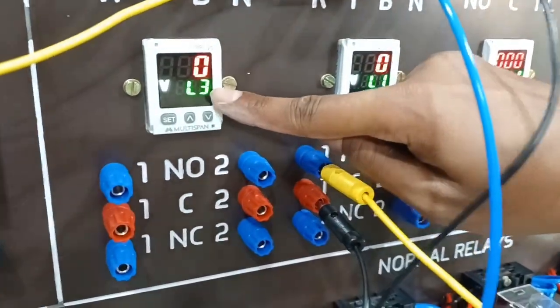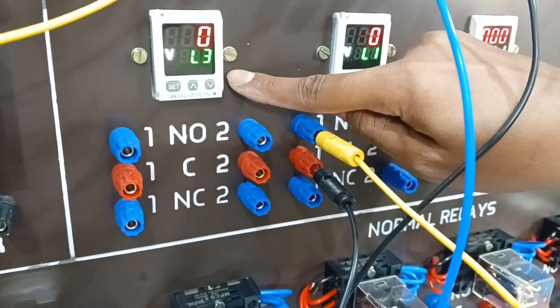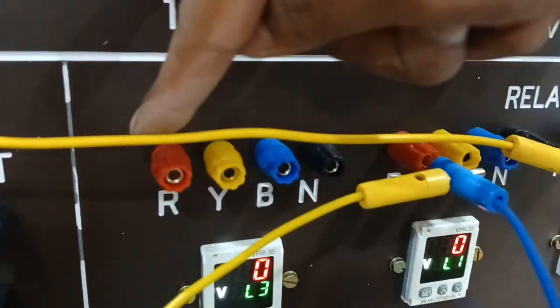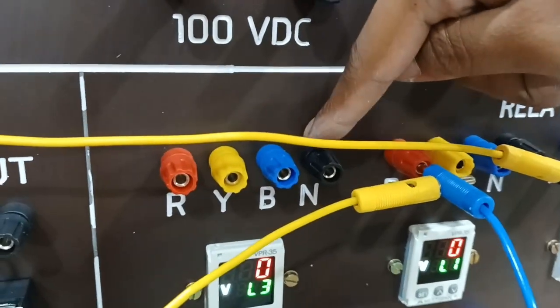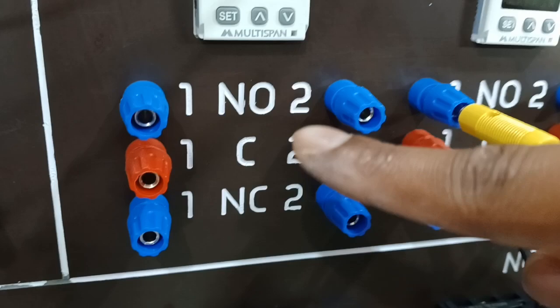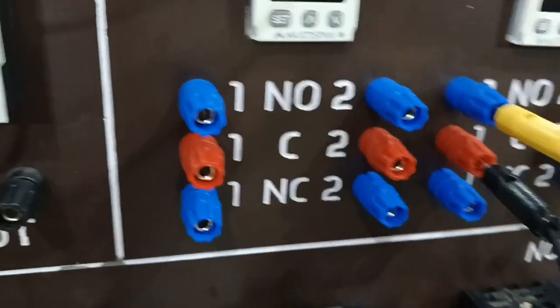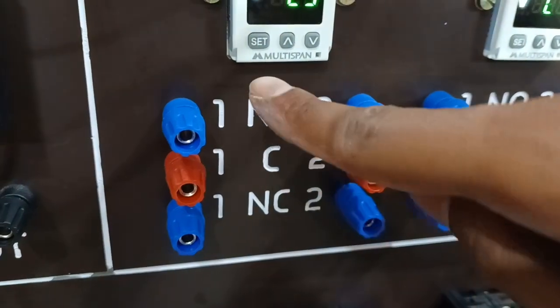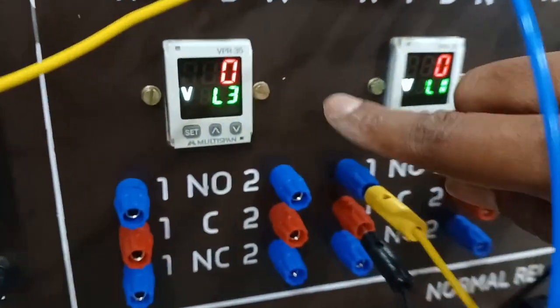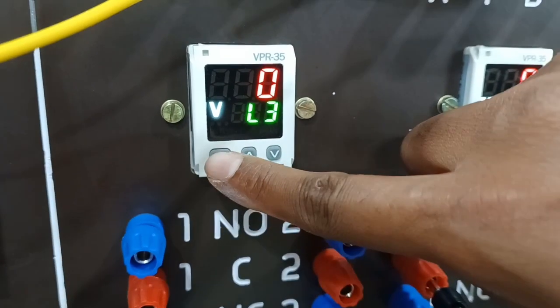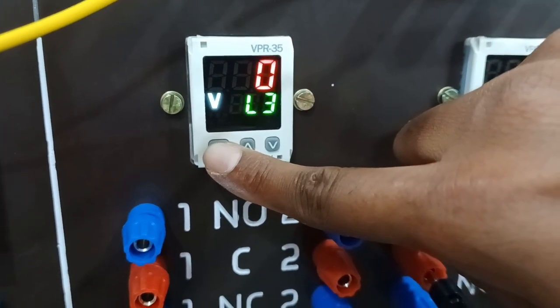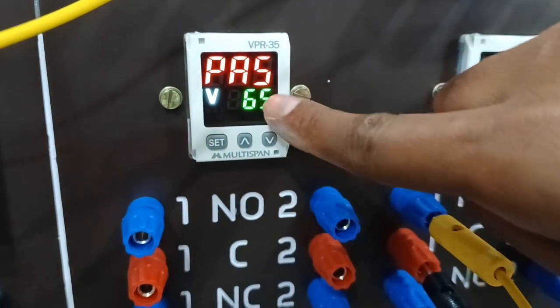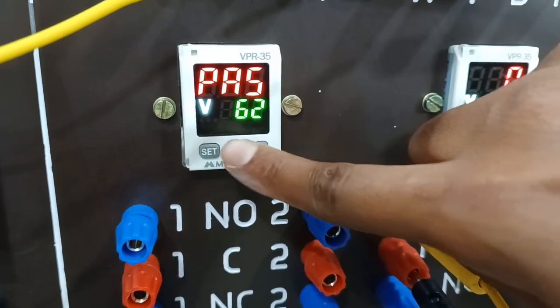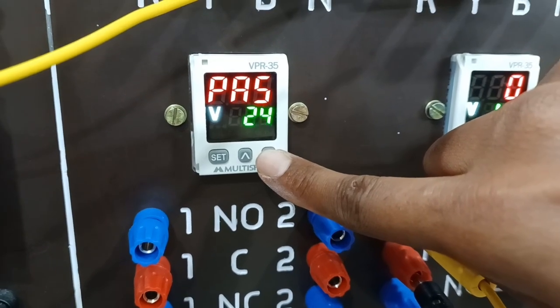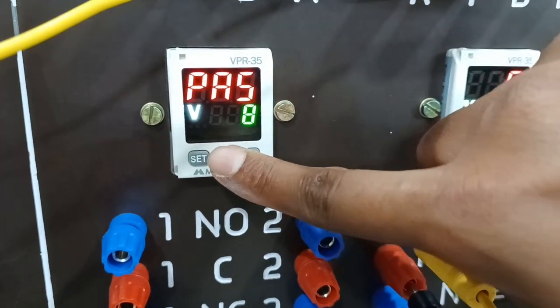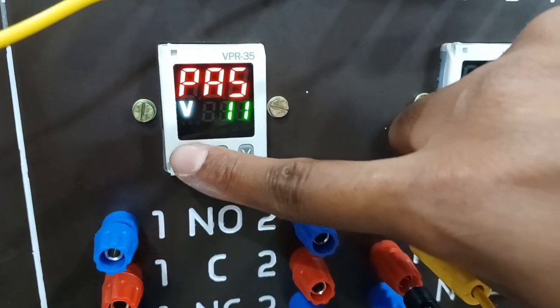Now coming to these two voltage protection relays. These are the relay voltage input terminals. These terminals are relay contacts: NO, common, NC. Two channels. This is channel 1, this is channel 2. Coming to the programming menu, same procedure. Press the set key for 5 seconds. It will ask for a password. The password will be 11. So password 11 we have entered.